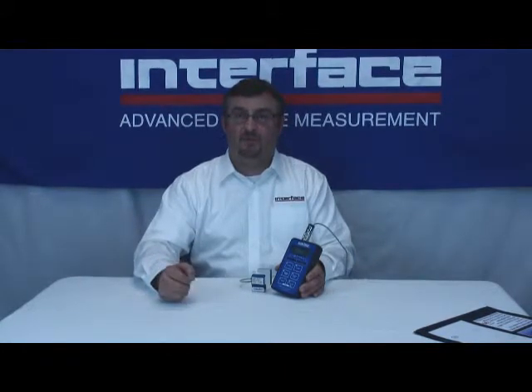Now the real advantage of that is if you have multiple load cells and only one meter. Each time you hook up a new load cell, all you have to do is allow the TEDS feature to self-scale the indicator, and then you're good to go. No complicated calibration procedure necessary.